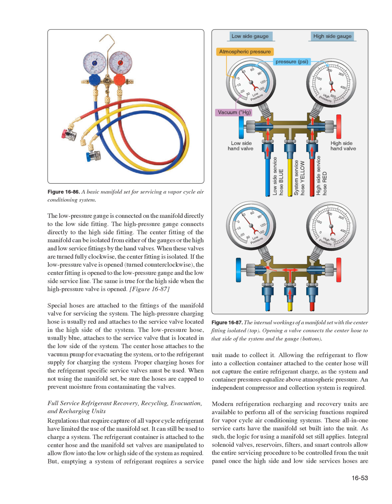Figure 16-87, special hoses are attached to the fittings of the manifold valve for servicing the system. The high pressure charging hose is usually red and attaches to the service valve located in the high side of the system. The low pressure hose, usually blue, attaches to the service valve that is located in the low side of the system. The center hose attaches to the vacuum pump for evacuating the system, or to the refrigerant supply for charging the system. Proper charging hoses for the refrigerant-specific service valves must be used. When not using the manifold set, be sure the hoses are capped to prevent moisture from contaminating the valves.